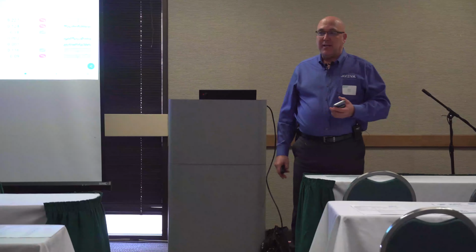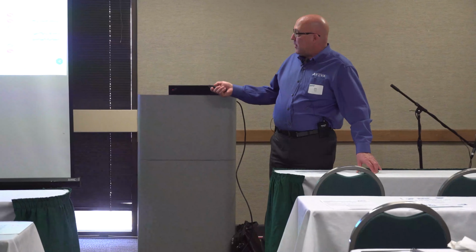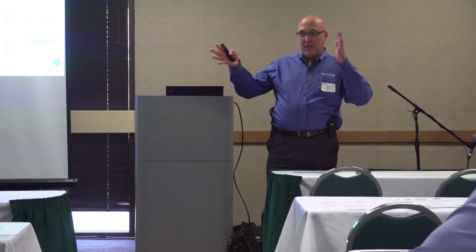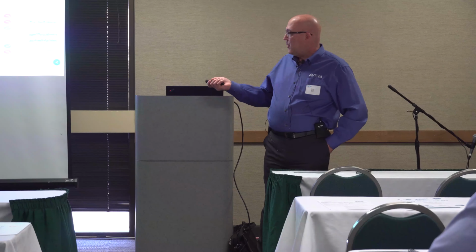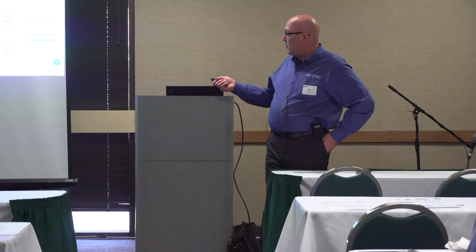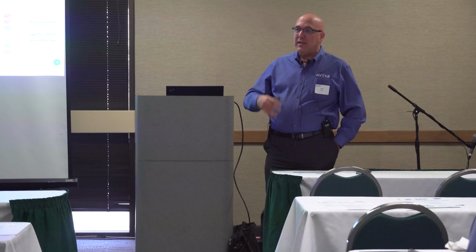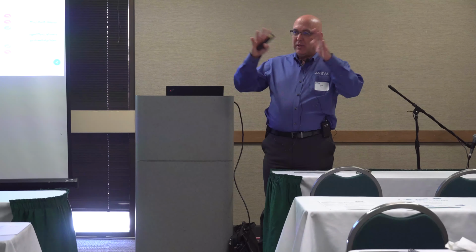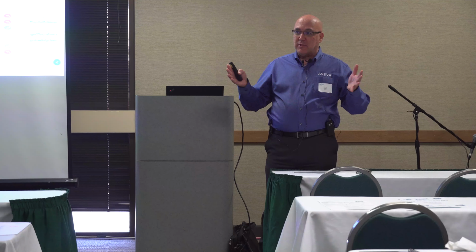And the first thing I get when I do that is the status board. The status board will tell me the live value, the current value of the tag, where the trending is headed for that particular value, and a real-time and historical trend of that information. You can pick predetermined time ranges, or you can customize and see them. I can then change the graph using this little graph button. I can change it to a trend, a grid, or statistical data. If you've ever looked at analog summary in the historian, that takes any high fidelity tag and converts it to statistical data, a statistical record.